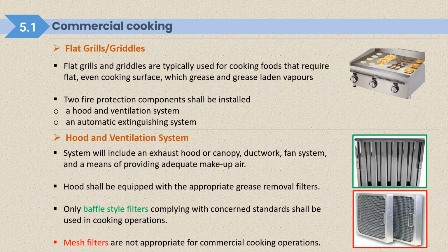Hood and ventilation system. There are two types of filter you can see right on the slide. One is Baffle style filter and the other is mesh filters. So we are talking about the hood and ventilation system. The system will include an exhaust hood or canopy, ductwork, fan system, and means of providing adequate makeup air, that is supply air. The hood shall be equipped with the appropriate grease removal filters. So every hood will be provided with grease removal filters.